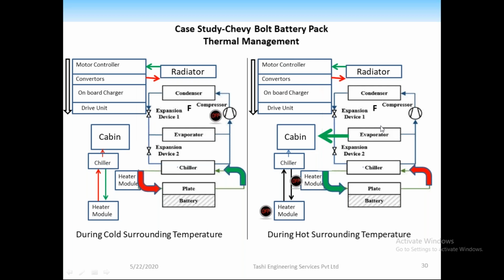A frequent question that comes up is this: if I'm making a vehicle, I know the average heat generation value will be say 2000 watts—that's the heat load. But at high load conditions, like a gradient climb or heavy loading, the maximum could be say 6000 watts. So should I select my compressor and condenser sizing as per 6000 watts, or as per the average heat load?